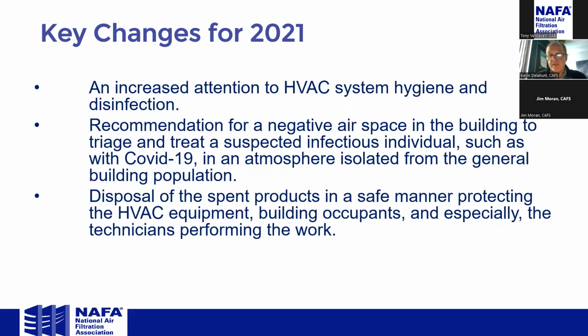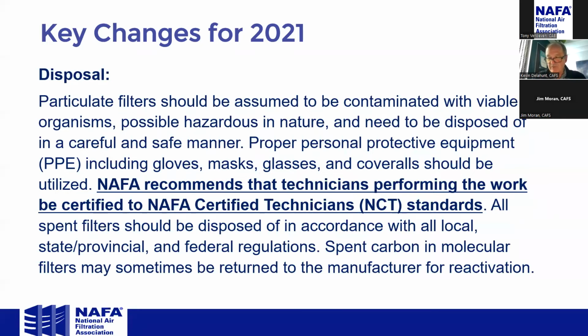Disposal is another issue with filtration right now, and disposal of spent products needs to be performed in a safe manner, protecting the equipment, the building occupants, and especially the technicians performing the work. Again, another push for the training so that the people changing the products have a better understanding of why, how, and what they're doing when they're changing the filters. So again, disposal: particulate filters should be assumed to be contaminated with viable organisms. We know SARS-CoV-2 is airborne, ergo, it should be considered that the filter could be contaminated with that at the point in time that it's changed. So it's contaminated with viable organisms, possibly hazardous in nature, and needs to be disposed of in a careful and safe manner.